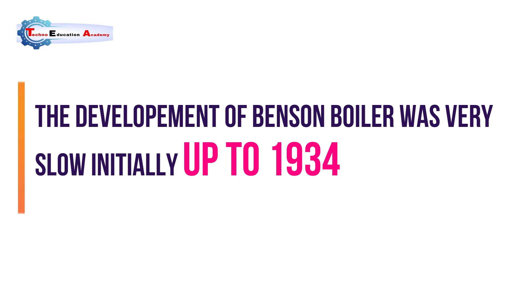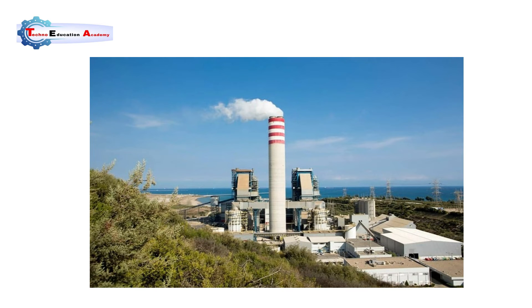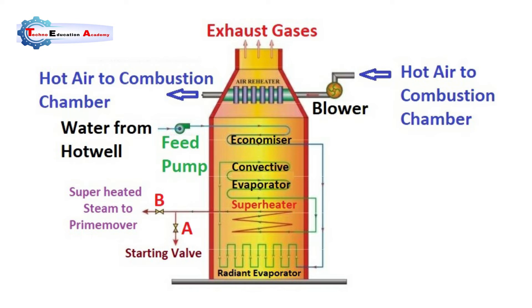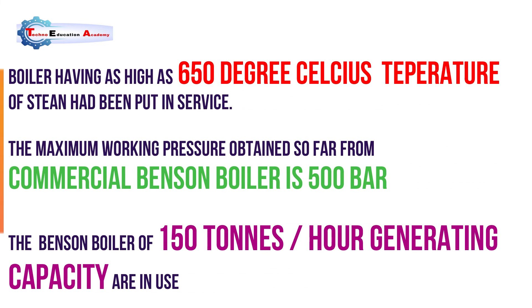The development of the Benson boiler was very slow initially up to 1934. After realization of its advantages, several boilers were built and the post-war era gave special impetus to its development. It has become customary in Germany to install Benson boilers in power stations. Boilers having as high as 650°C steam temperature have been put in service, and the maximum working pressure obtained from commercial Benson boilers is 500 bar. Benson boilers of 150 tons per hour capacity are generally in use.